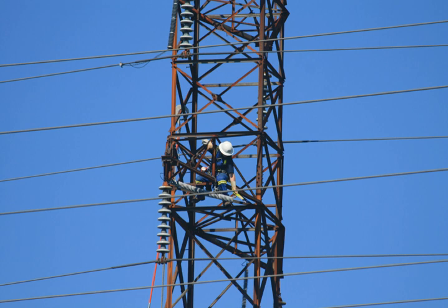A lightning arrestor, alternative spelling lightning arrester, also called lightning diverter, is a device used on electric power systems and telecommunication systems to protect the insulation and conductors of the system from the damaging effects of lightning. The typical lightning arrestor has a high voltage terminal and a ground terminal. When a lightning surge, or switching surge, which is very similar, travels along the power line to the arrestor, the current from the surge is diverted through the arrestor, in most cases to earth.